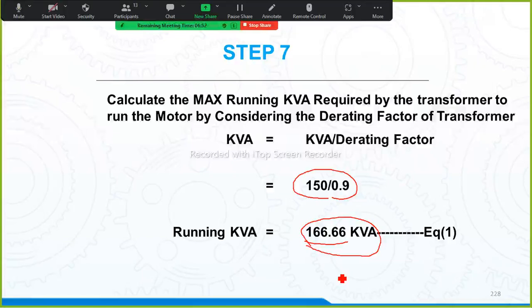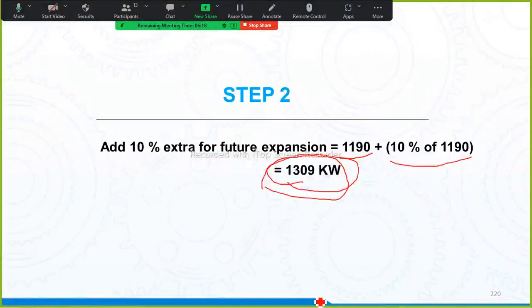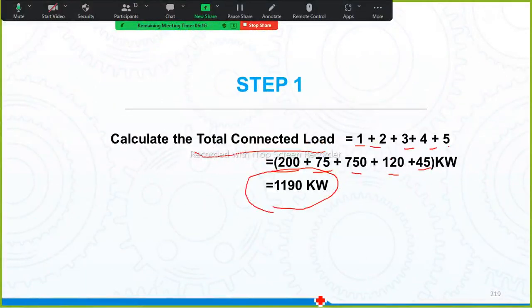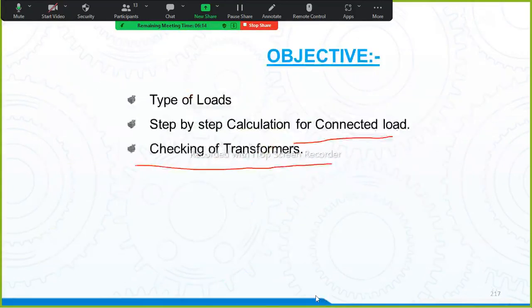Which kVA is this? This is called the running kVA, but at the time of starting, it will take high power, yes or no? Yes sir. So we have to use a starter. You also fit a starter, because it will take high current at the time of starting. Why do we fit a starter? To reduce the starting current. But even though you are putting one, we need to consider the maximum starting current and calculate the kVA. Now when you go with the maximum, what is the maximum kVA that the motor will take? Now we will see.